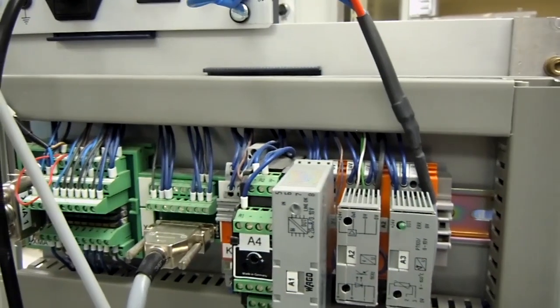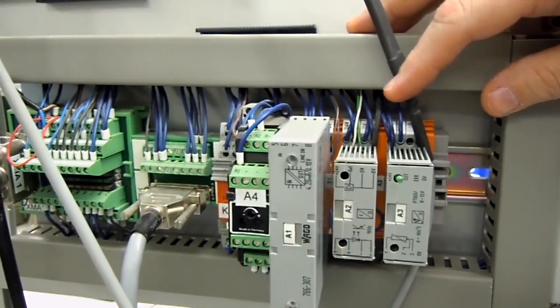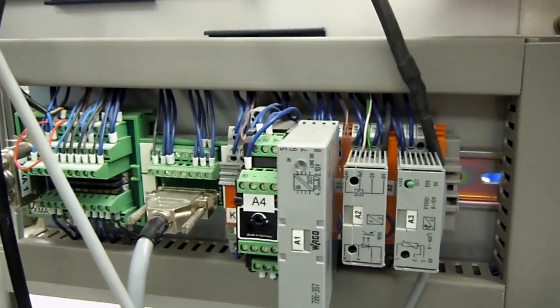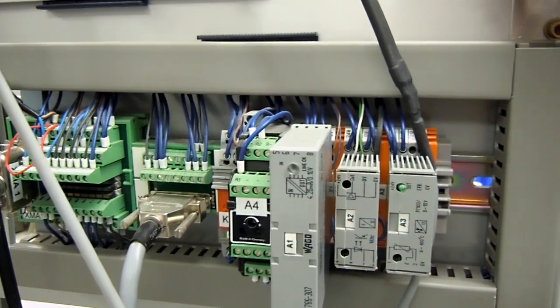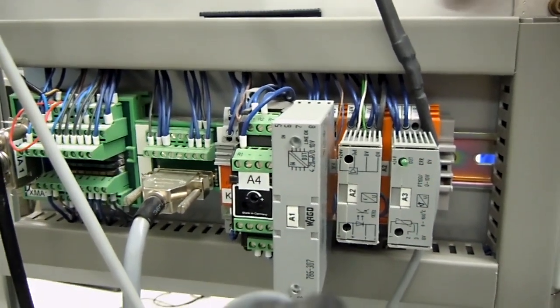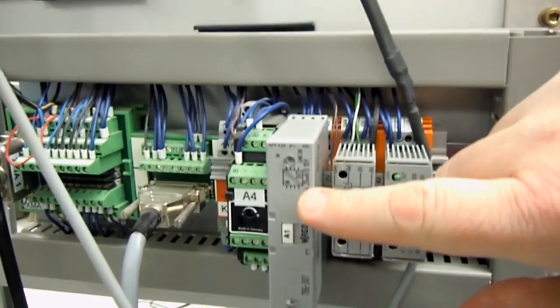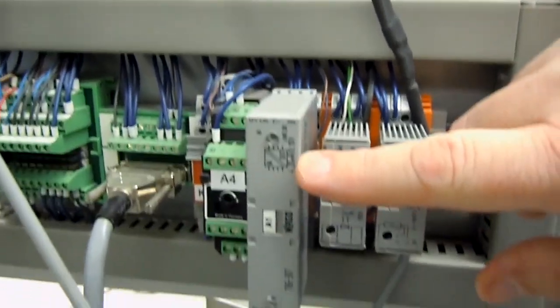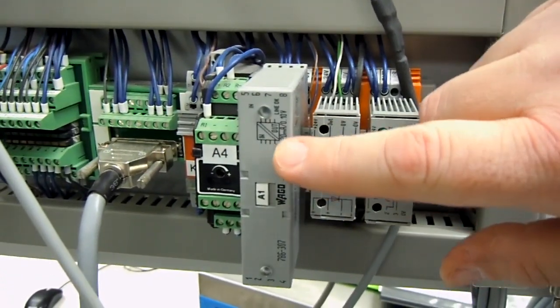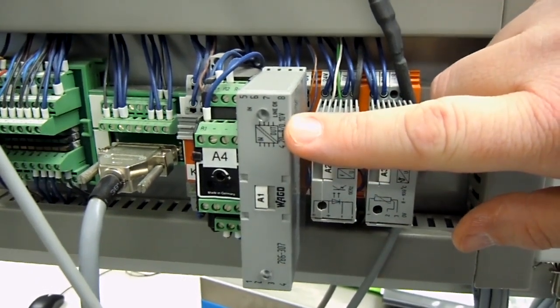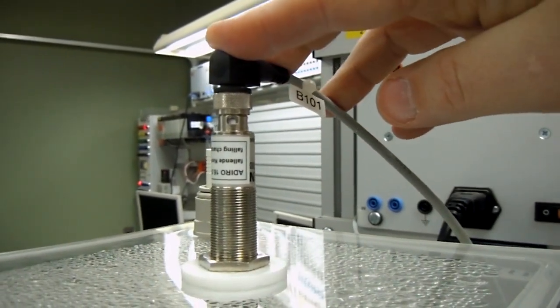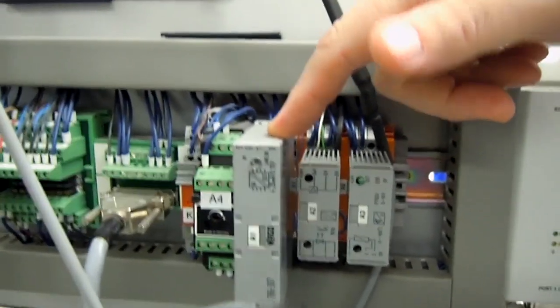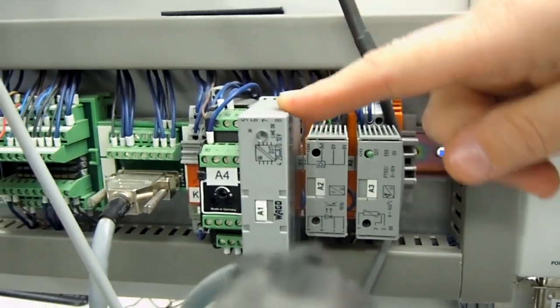All right, there are 3 converters in this system here that convert signals from 3 of the sensors to outputs between 0 and 10 volts. The first one on the left here, you can see that it indicates an input in the range of 4 to 20 milliamps to an output of 0 to 10 volts. That's actually coming from this sensor over here, which is the level sensor. So it measures 0 to 300, produces an output of 4 to 20 milliamps, and then an output of 0 to 10 volts that we feed into our PLC or the Festo system.